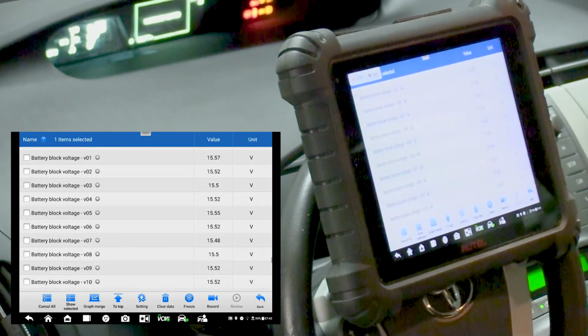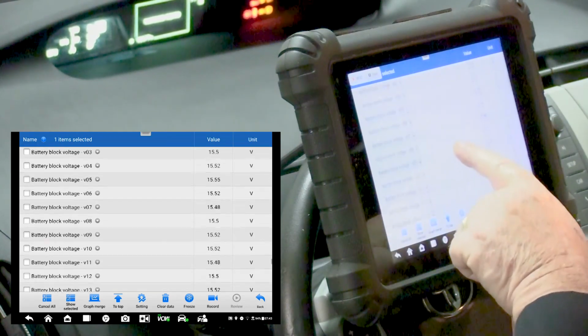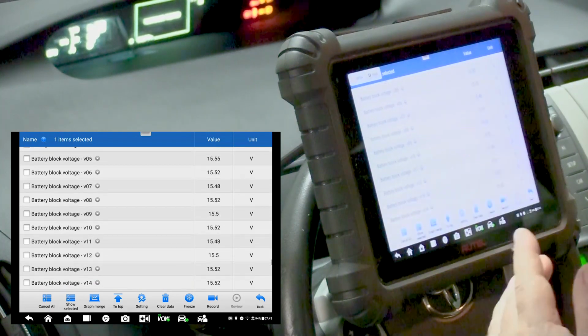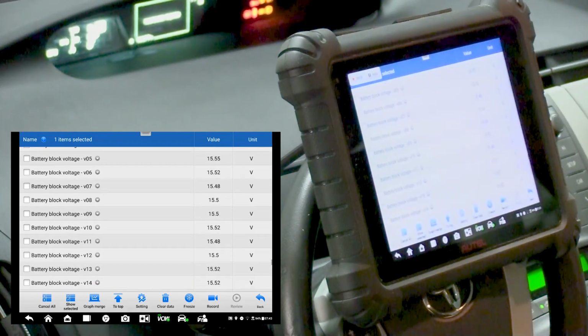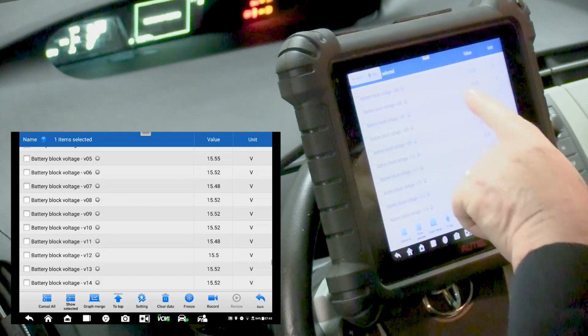These are the battery block voltages, and you can see that there are 14 of them. That makes sense, because it's 28 modules made up of 6 cells each, and the modules are paired together to form these battery blocks. Since it's 7.2 per module, we're looking at around 14.4 baseline for the block. If it's fully charged, you may see it go as high as 17. If we see anything much below 13, that's a problem.